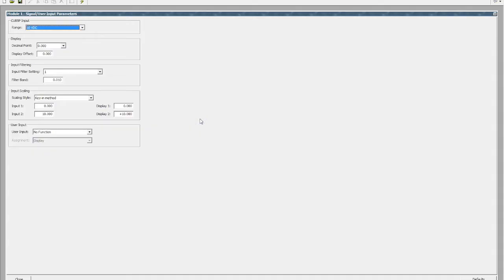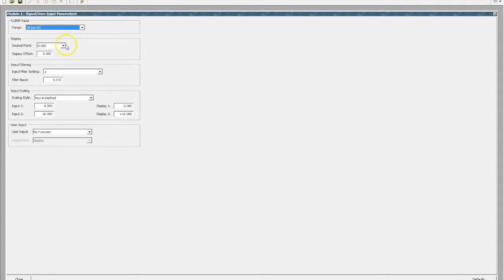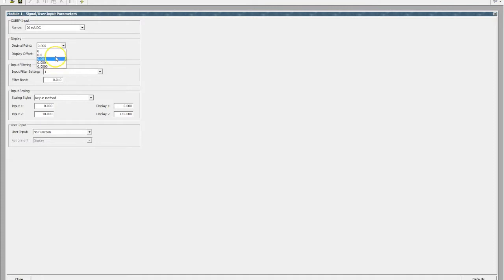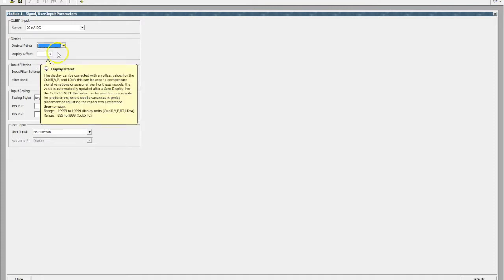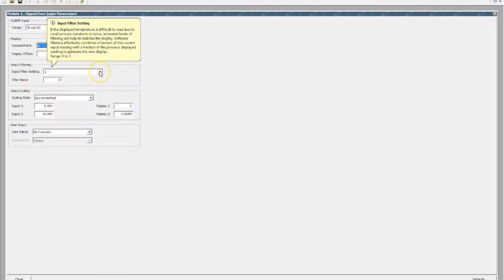If we quickly look at the signal input, we can nominate what input type we've got, so they are universal for both voltage inputs and milliamp inputs. Let's select milliamp. We can nominate our decimal point to suit the application, we can also choose whether we want it to have a display offset, so that's obviously applicable to the particular sensor that we're using. We can also nominate our filter time.